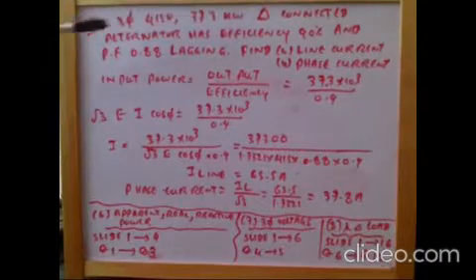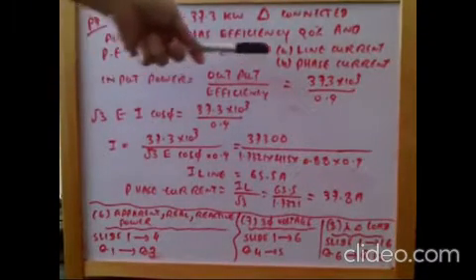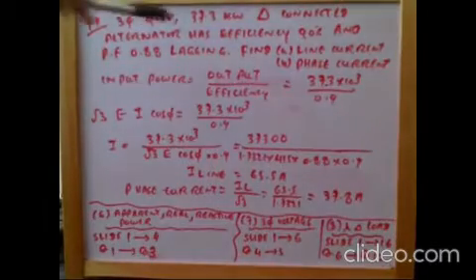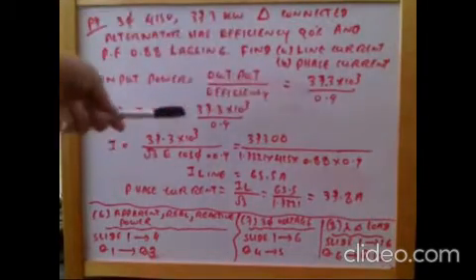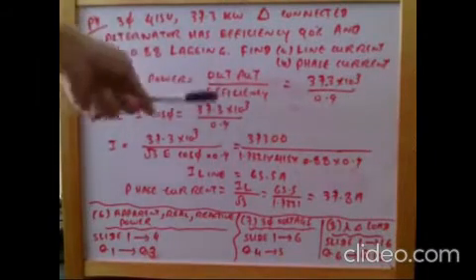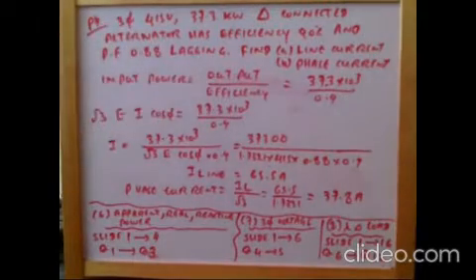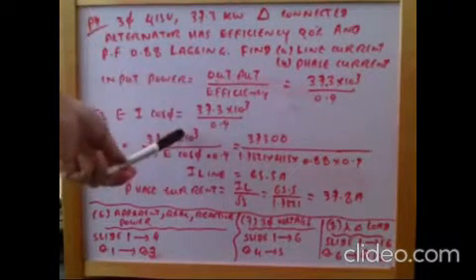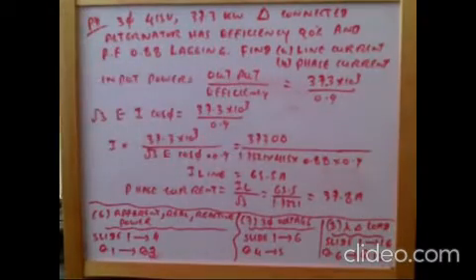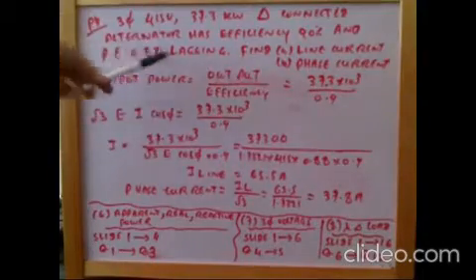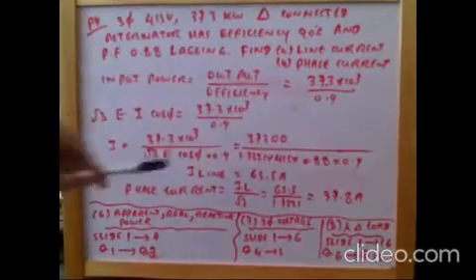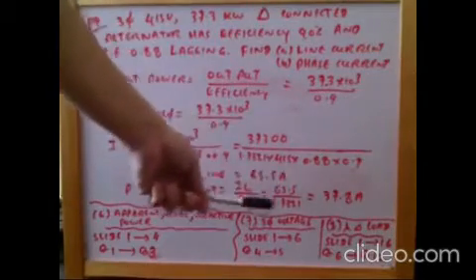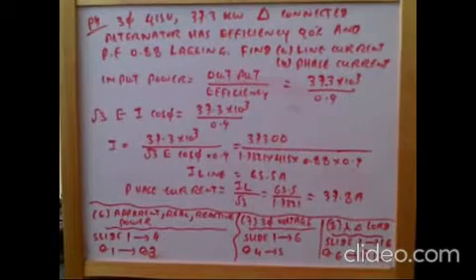Three-phase system: 415 V, 37.3 kW, delta-connected, 90% efficiency, power factor 0.88 lagging. Find line current and phase current. Input power = output / efficiency = 37.3 × 10³ / 0.9. Then, input power = root 3 × E × I × cos φ, rearranging: I = power / (root 3 × E × cos φ). With root 3 = 1.732, E = 415 V, cos φ = 0.88, line current = 65.5 A. Phase current = 65.5 / 1.732 = 37.8 A.